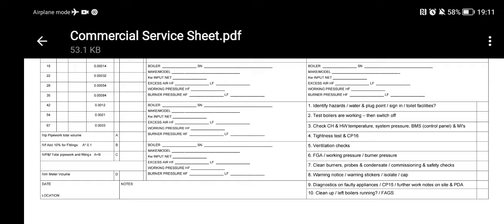Test boilers are working. Before you touch a boiler, check — is the boiler working? The customer may say it was working before you touched it. So before you put your hands on it and clean the burner out, verify it was actually working. Also establish where the switch live is, and how it goes into high and low.